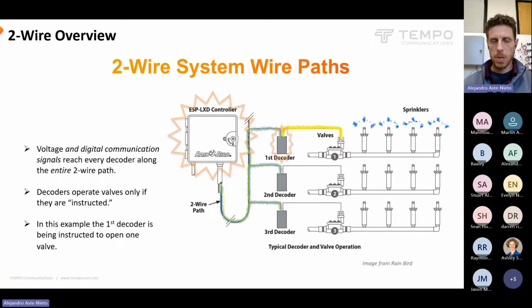So, again, some systems only have voltage when there's a zone being operated, and there's no two-way communication happening when the system's idle. And therefore, there's nothing for your clamp meter to measure, by the way. We'll talk about how to handle that, but just understand that for some systems, there's no current flowing when the system is idle. For other systems, there is.